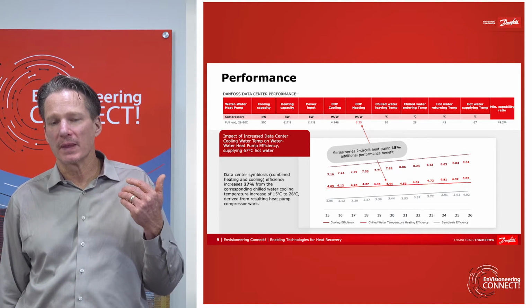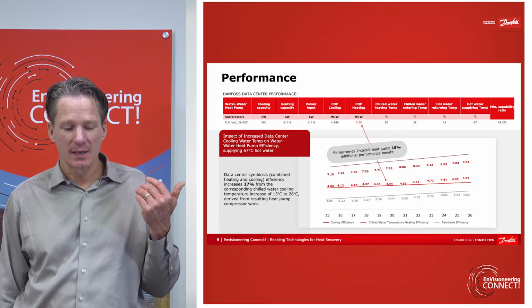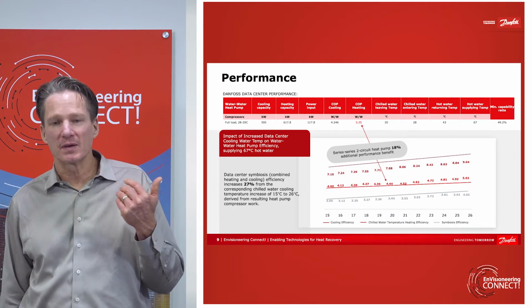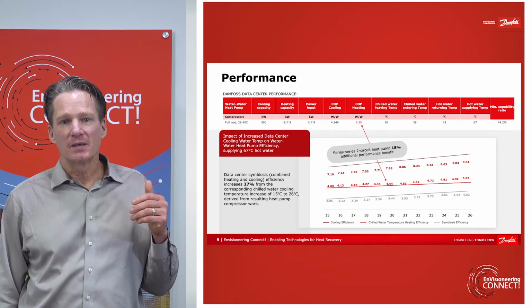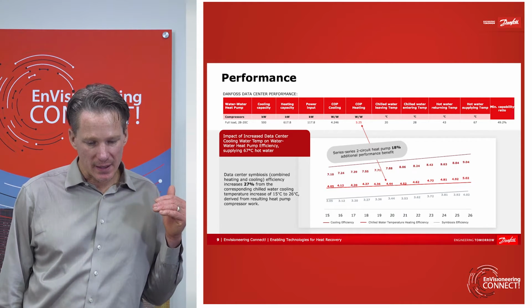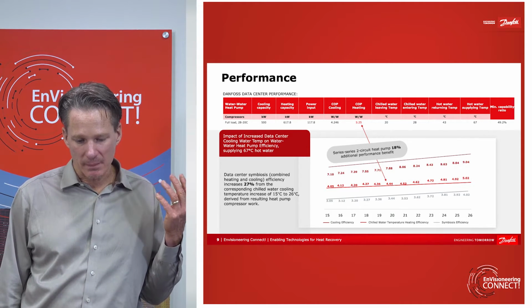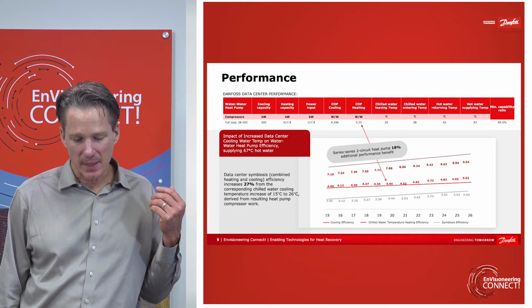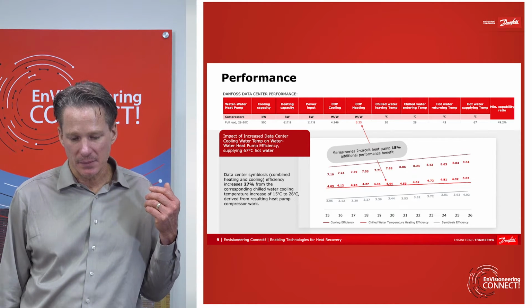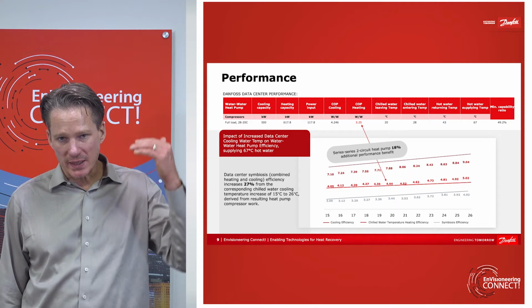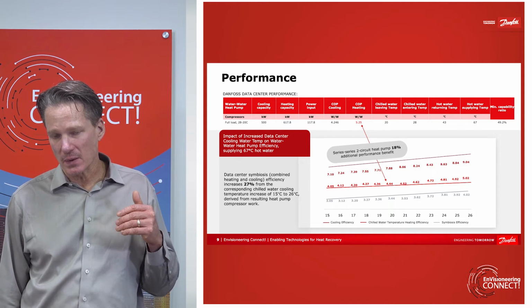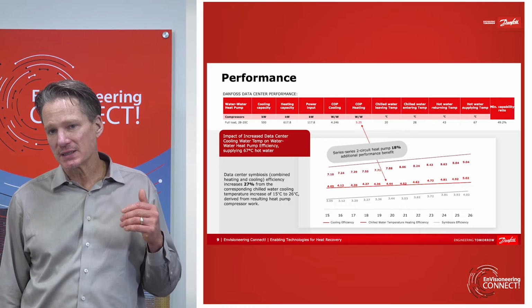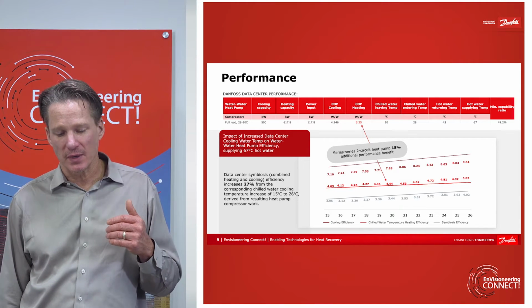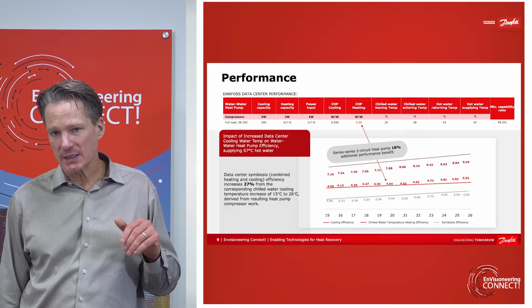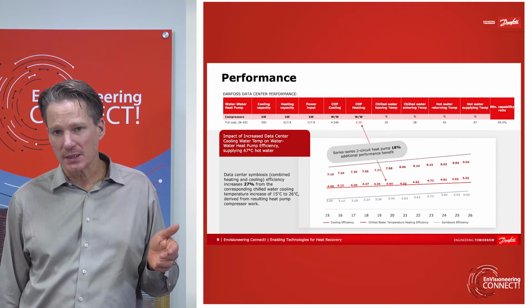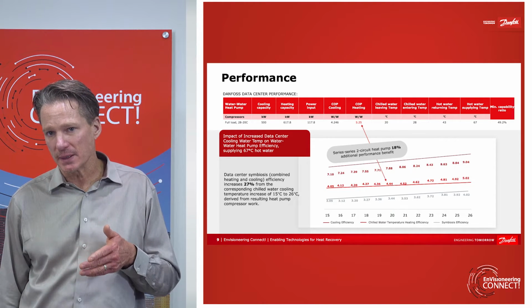So, for example, if you're cooling a data center at 15 degrees C, or about 54, 55 degrees Fahrenheit, you are going to be operating at an efficiency on a water-to-water heat pump based system or water-cooled chiller based system of about 3 to 3.5 COP. That's with that higher heat rejection temperature of the water-to-water heat pump. As that cooling temperature increases up to 25 degrees C, with everything else staying the same, you increase from roughly a 3 COP to up to a 4 COP.